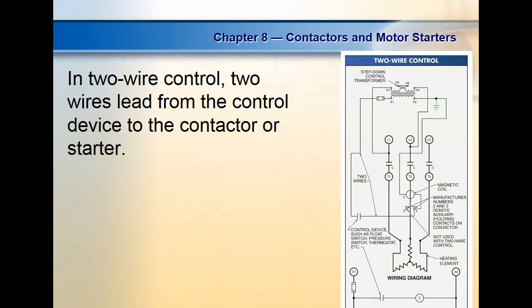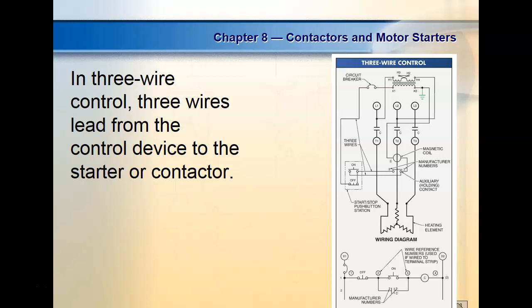So we have 2-wire control. Basically 2-wire controls and 3-wire controls. If we have a seal-in, you can call it 3-wire control. If you don't have one, you can call it 1-wire. I'm sorry, 2-wire. We never have 1-wire control. In 2-wire control, 2 wires lead from the control device to the contactor or starter. So 1, 2. This would be a 2-wire circuit, right? Okay? And we're talking about wire numbers. We call this a 3-wire circuit because there are 3 wires from L1 over to the control device. 1, 2, 3. And this is why it's sometimes called a 3-wire circuit. Are we okay?